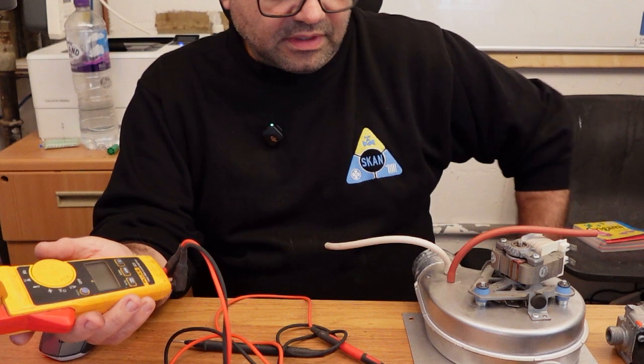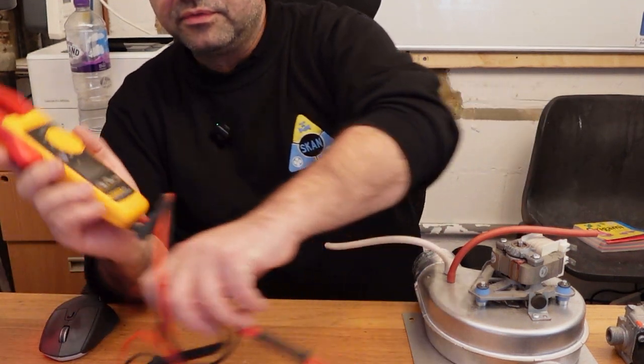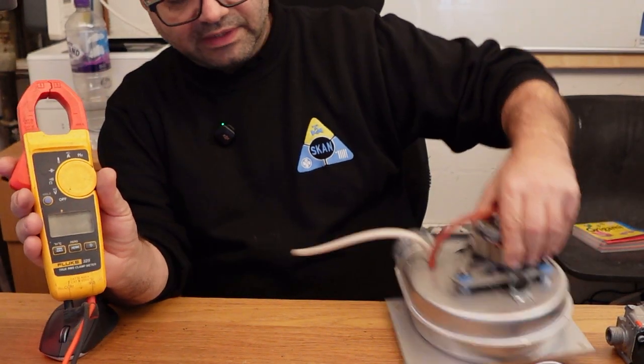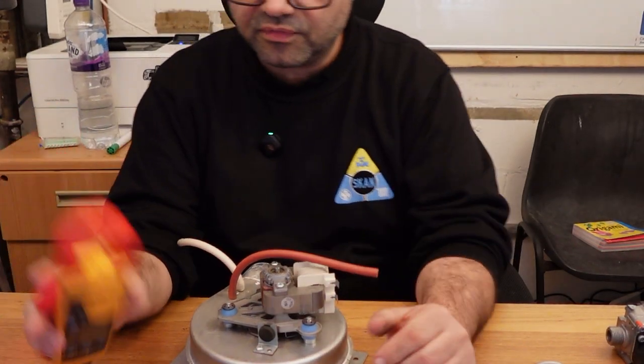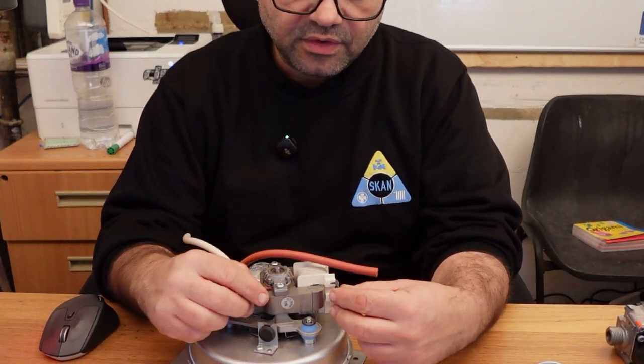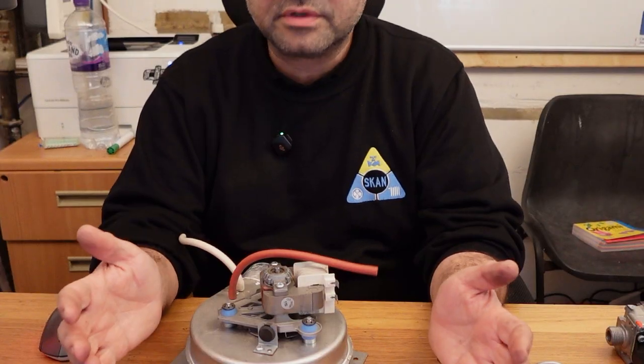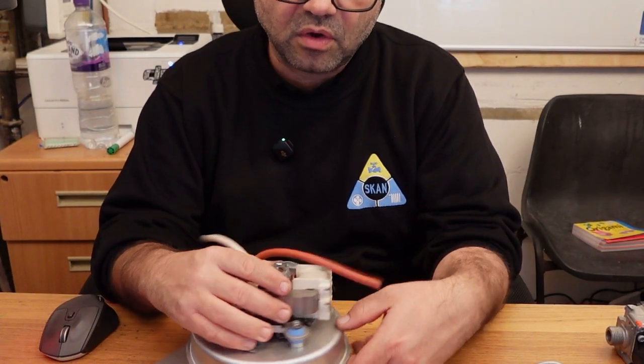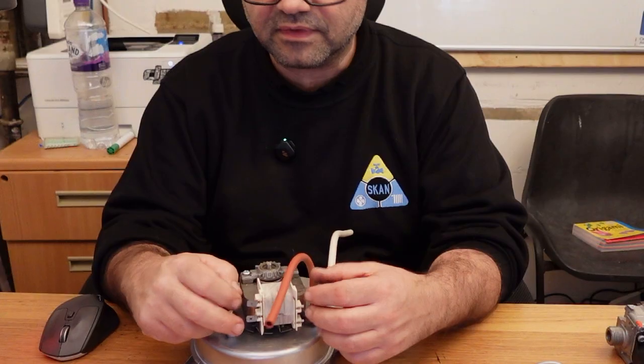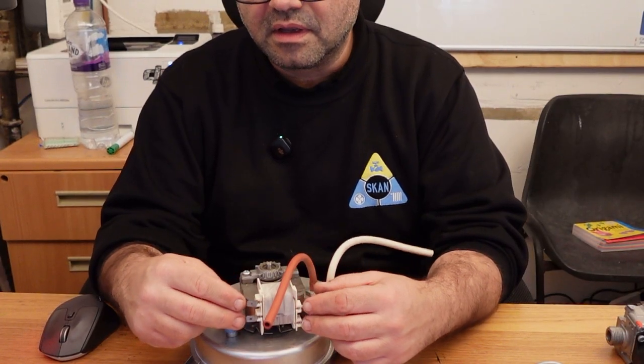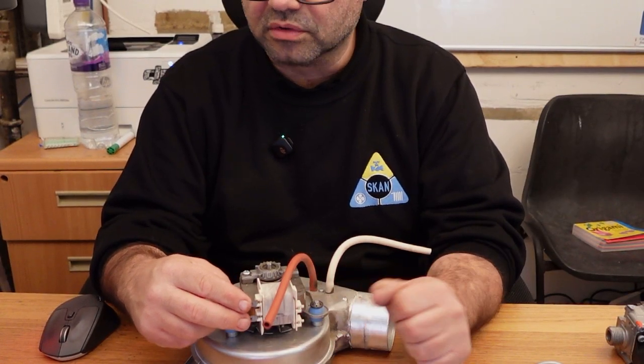Let's crack on. I have in front of me an extractor fan. The extractor fan has windings, and those windings have an ohm resistance, which we can easily check with the ohm meter to see if it's at acceptable levels or not.